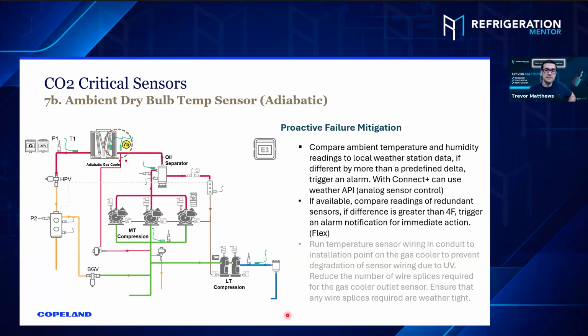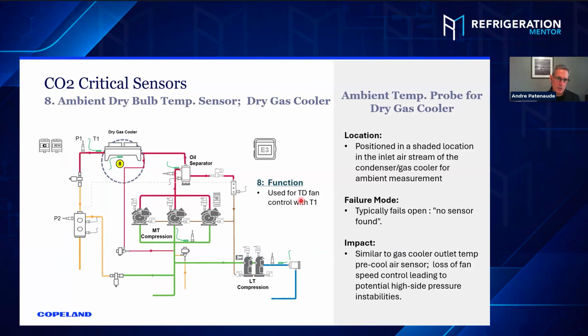And then there are some things you can do with 7B proactively. You can compare the ambient temperature and humidity readings to local weather stations. If they're way off, then you've got an issue. If that retailer has Connect Plus, then you can use the weather API with Connect Plus and compare the sensor to that. So there are some things you can do in order to double check that.